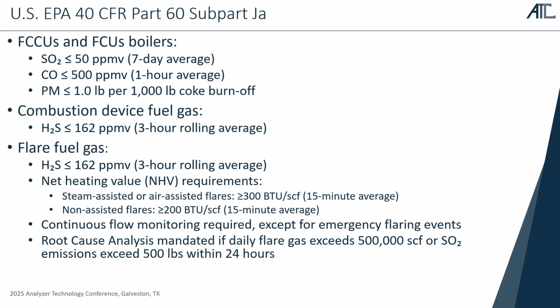So to break it up a little bit, the first ones are your traditional CEMS, where you have the effluent post-combustion going into a stack, a small stack, and then being released into the atmosphere. And you have various analytical devices and methods to measure that. And the next part is the pre-combustion. Of course, you can't really measure the effluent of a flare because it's being burnt already in the open air. So we'll get into how we achieve that as well.